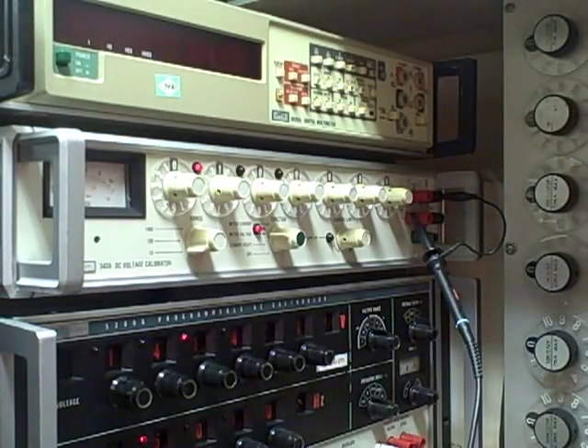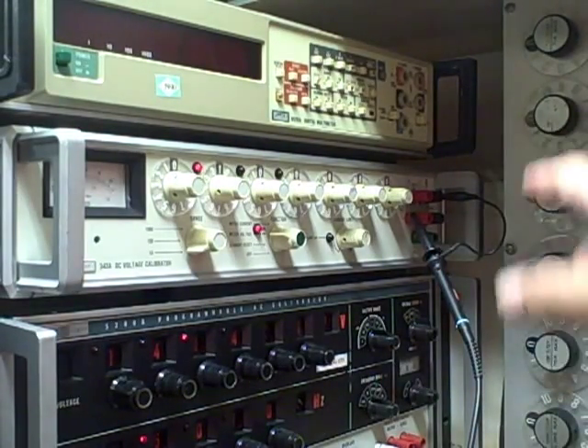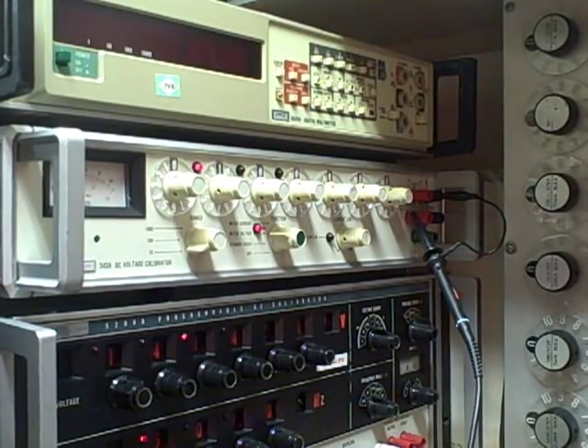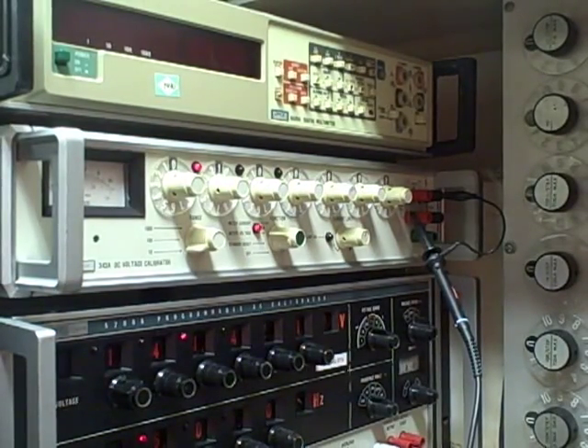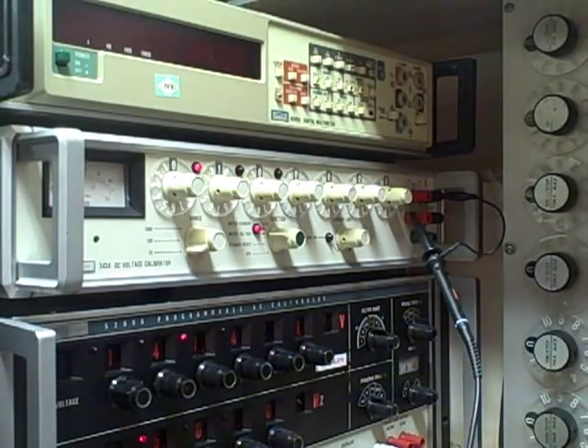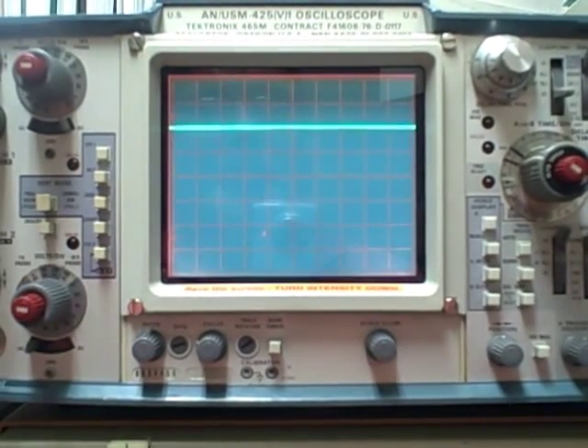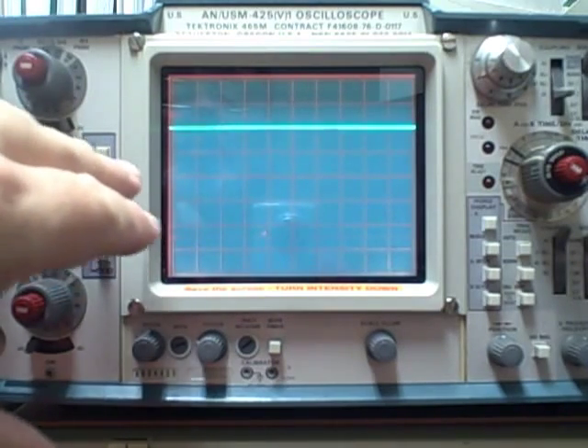So everything that I'm measuring at the scope end is 1/10 of what I actually have at the tip of the probe. By doing that, I'm able to provide myself the voltages I need at the scope with less noise, because I'm actually providing something 10 times larger and then dividing it down. Just a little explanation as to what I'm doing here. Right at the moment we are putting in a tenth of a volt at my Fluke. We're dividing by 10, so we're really at 0.01 volt at the scope, and we are right now on 5 millivolts per division.